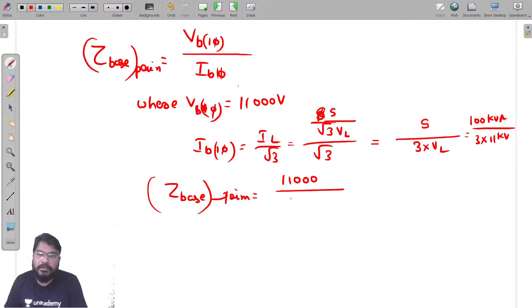So now Z base is equal to, what is Z base referred to the primary side? V base is 11,000 divided by, it's 100 kVA divided by 3 into 11,000. Now simplify: 11,000 squared divided by 100 kVA by 3. Now calculate the value of Z base.